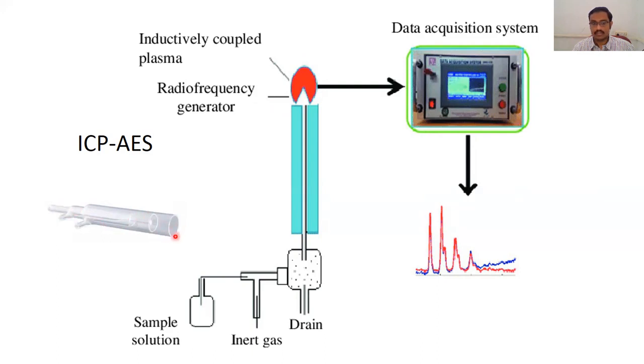radio frequency generator which is coiled over this ICP torch. So a quartz triple layer canister over which an RF generator is encircling and when a sample is made to burn in such a setup there is plasma which is produced at a very great temperature and at this temperature the atoms excite even better and the readings are even more reliable and more superior than your normal AES. Therefore this is a much greater advantage when we speak about AES and therefore presently all our laboratories are more and more moving into ICP AES which is a much better sensitive accurate and also reproducible technique.